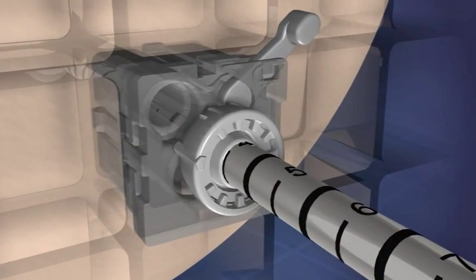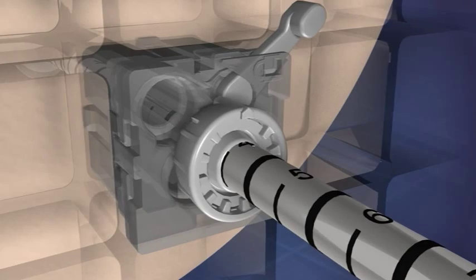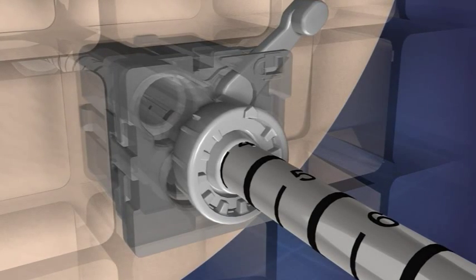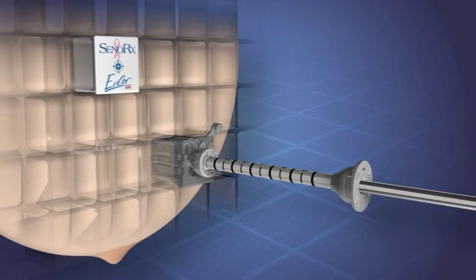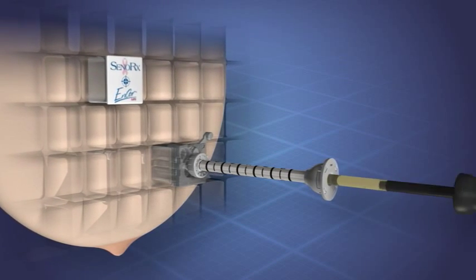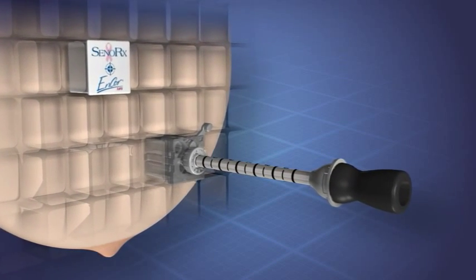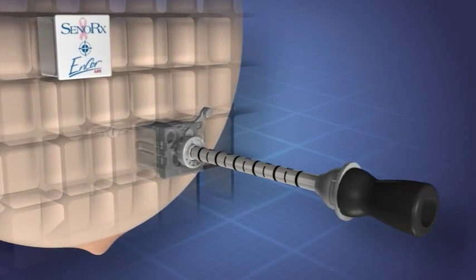Once this is done, the depth stop is slightly rotated clockwise to lock it into the locking block. The trocar is then removed and replaced with the patented Encore Viziloc obturator, which will allow for easy visual verification of position prior to sampling.